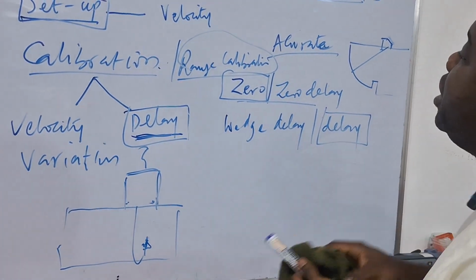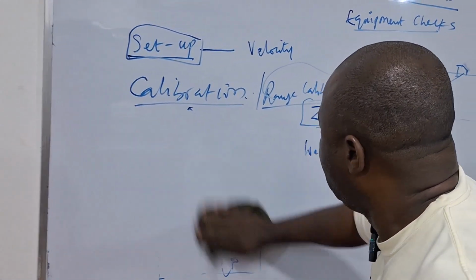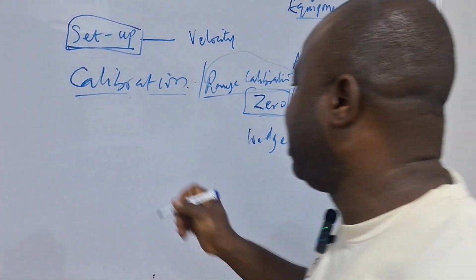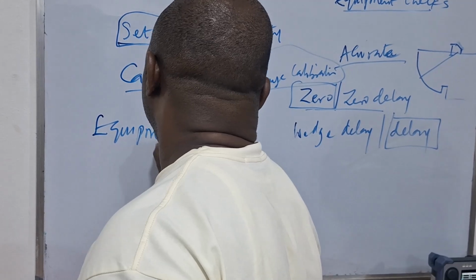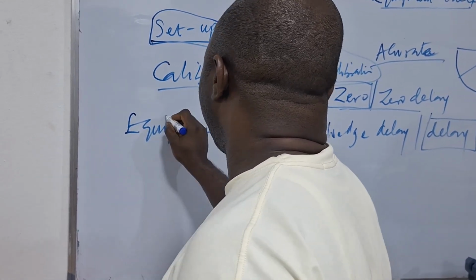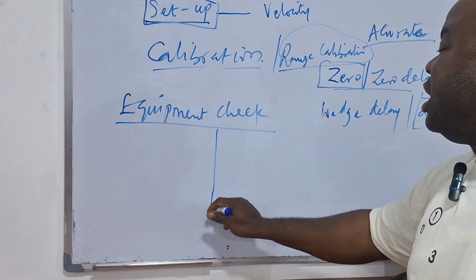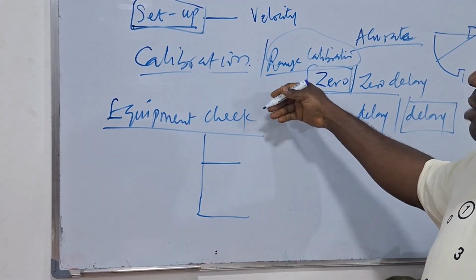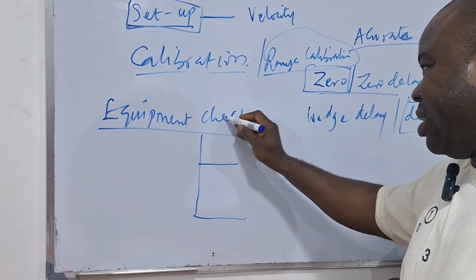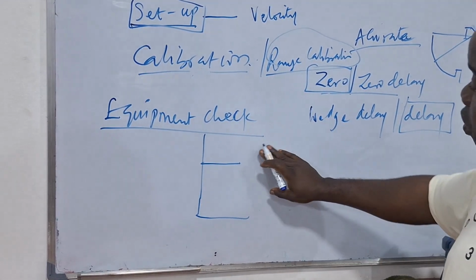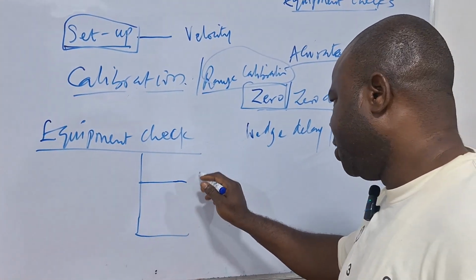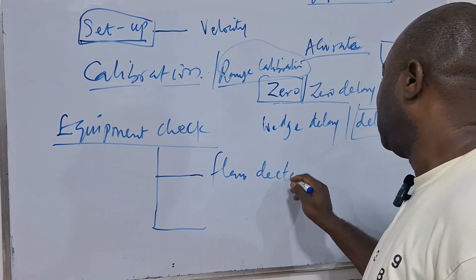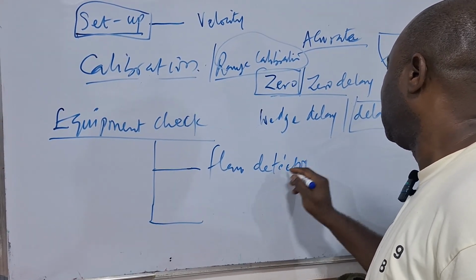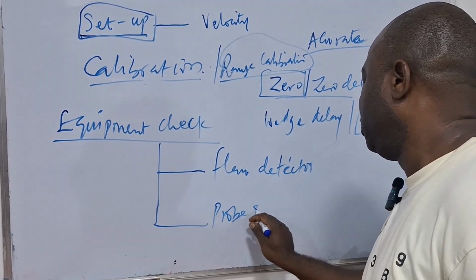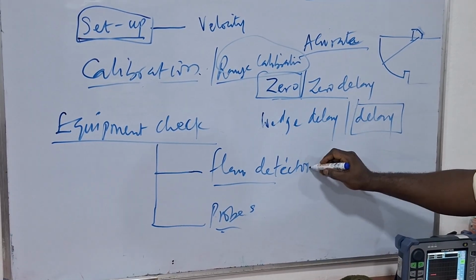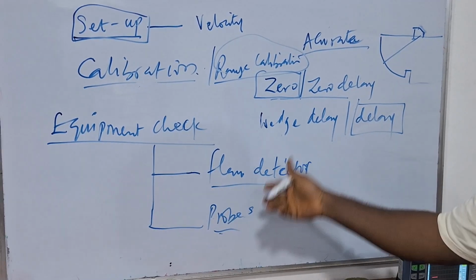That is for equipment calibration. Then the third term we often see is what we call the equipment check. A lot of times, UT inspectors don't do this, especially when the client does not ask or when there are no issues. When you come to equipment check, you can check either of these two: your flaw detector check and your probe check.